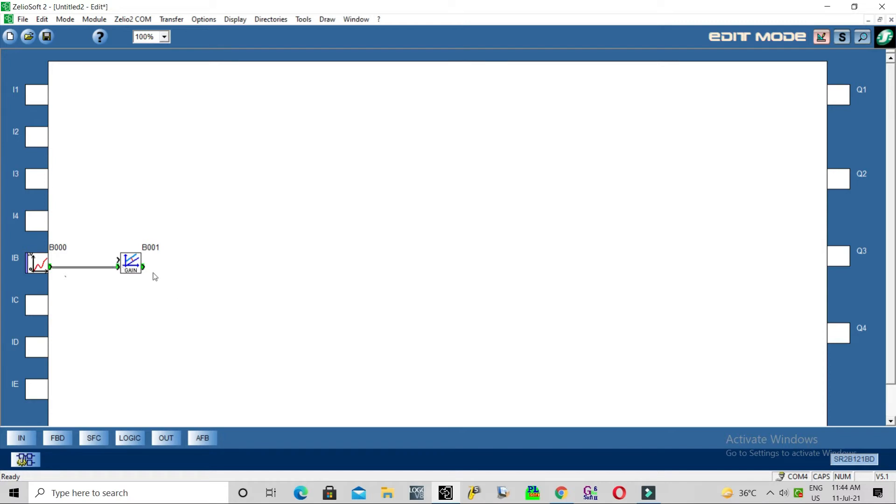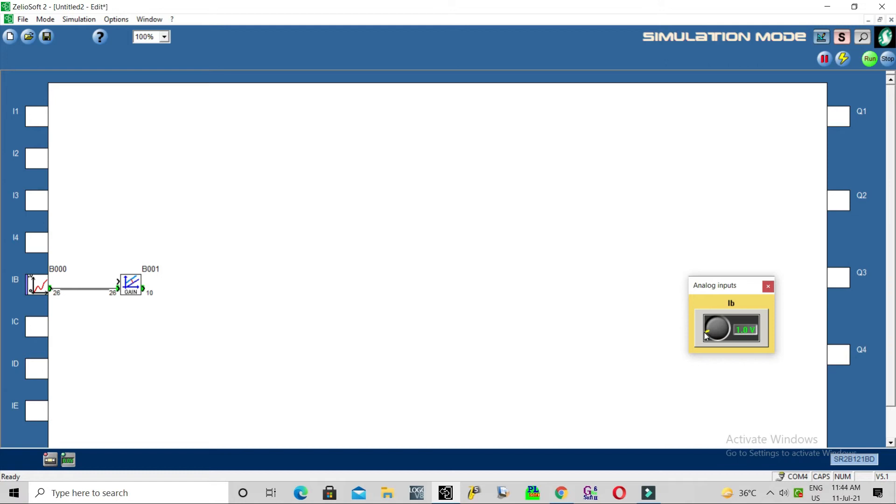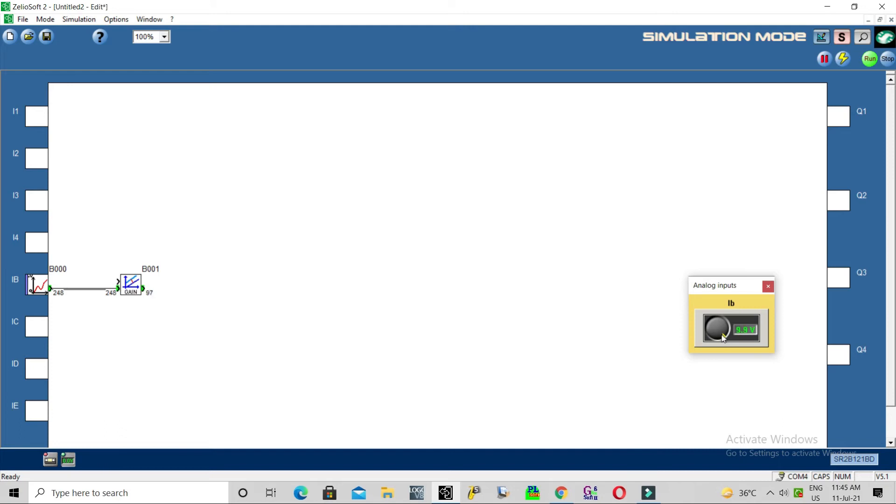Now we will check how it is working. Go to simulation run. Now the sensor is showing nothing - it is 0 when it is sending signal to the controller. Full scale is 10 volt. When our sensor is sensing 100 degree Celsius, that is almost 10 volt connected to 255, we have connected to 100. So when the controller sends 255 that means 100 degree Celsius.